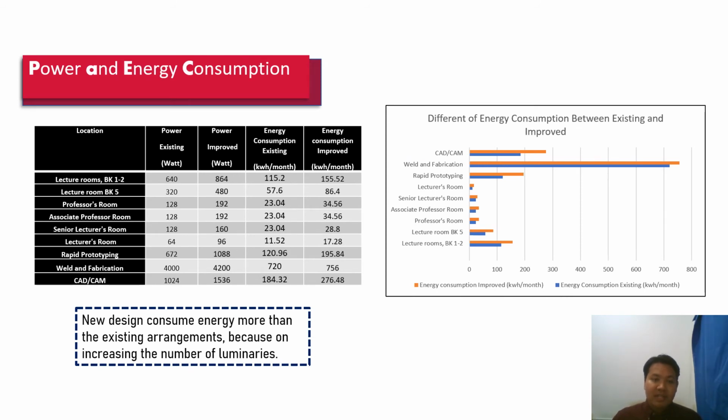Next, we have the result of the power and energy consumption between the existing luminaires and the improved design luminaires. The results show the new design consumes more energy than the existing arrangement. It is because of the increased number of luminaires.